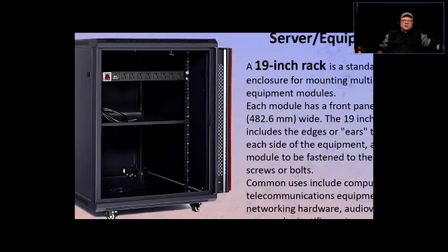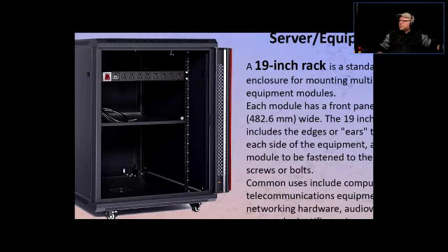What's standard about racks is they have rack rails and the equipment that is rack-mountable fulfills mounting standards to be mounted. You can buy any equipment rack and the sizing is the same — it's called 19 inches, from edge to edge. What do you see in a typical rack? You'll see a shelf mounted on those rails. A PDU — power distribution unit — is a very common thing for racks, because you don't want to run a bunch of power bars and extension cords.